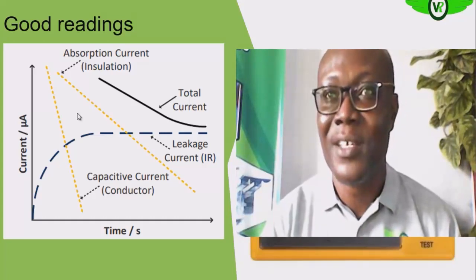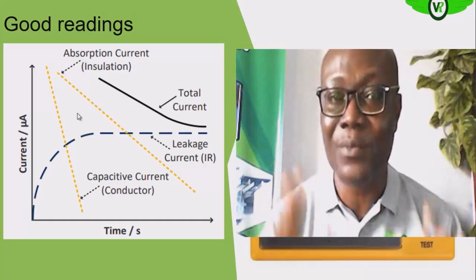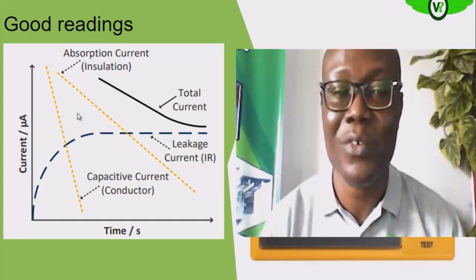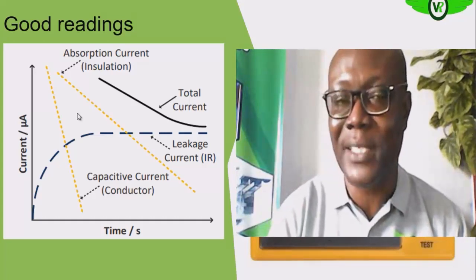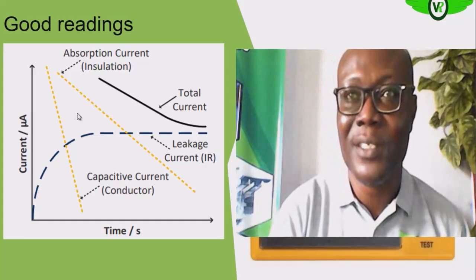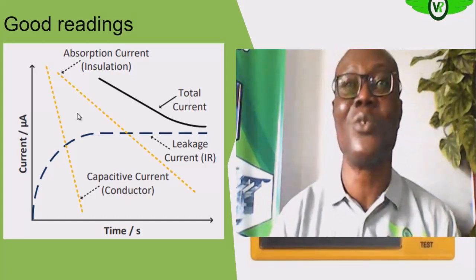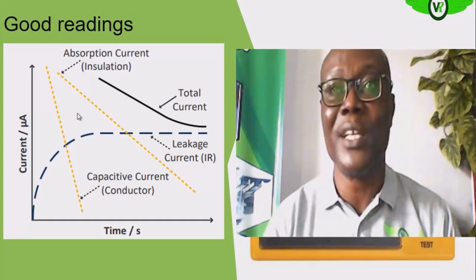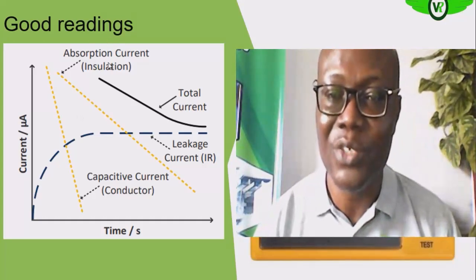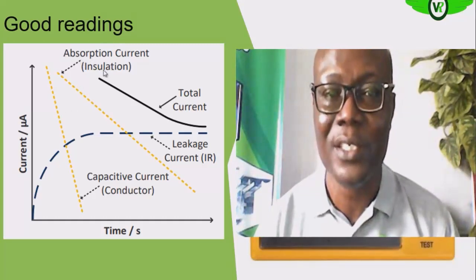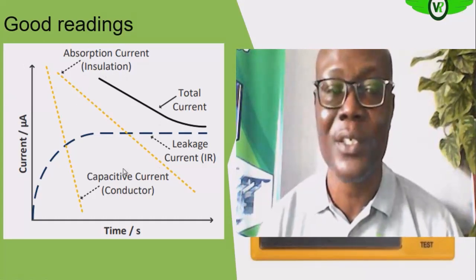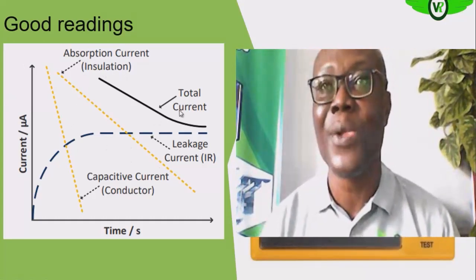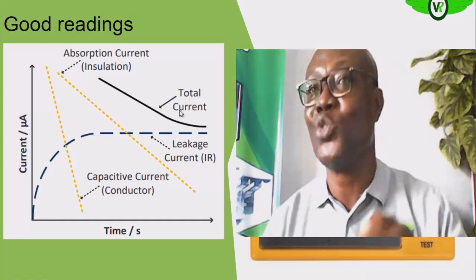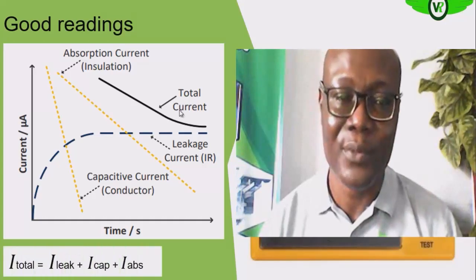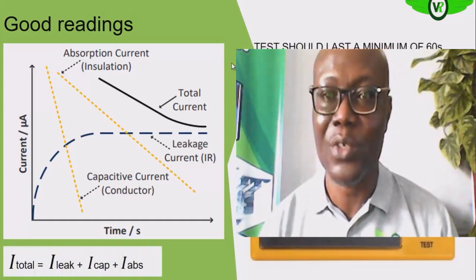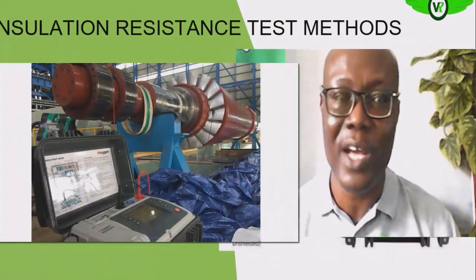Are we getting it? Remember, R is equal to V over I. So if I is high, R will be low. Okay, but if you allow some time to pass, the capacitive current would have disappeared, and then the absorption current will also disappear. So when that happens, what will be left is the leakage current. So whenever you go to carry out an IR test, you allow at least 60 seconds to pass, so that all of this will disappear, and then you have a reading that will be a true reflection of what you have. So the test should last a minimum of 60 seconds for you to have a good test.